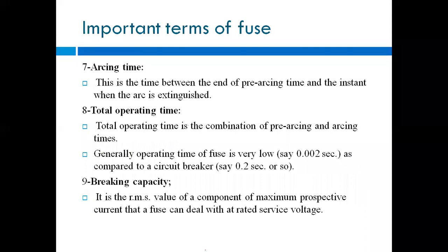Now the operating time of this fuse is very low. We can consider it almost 0.002 seconds, as compared to the circuit breaker. A circuit breaker requires almost 0.2 second, but for a fuse the time required is only 0.002 seconds, which is very little as compared to other protective devices.